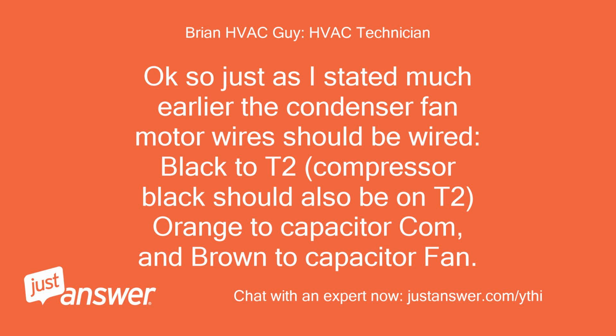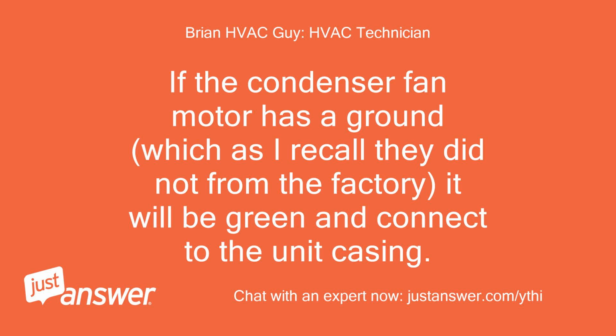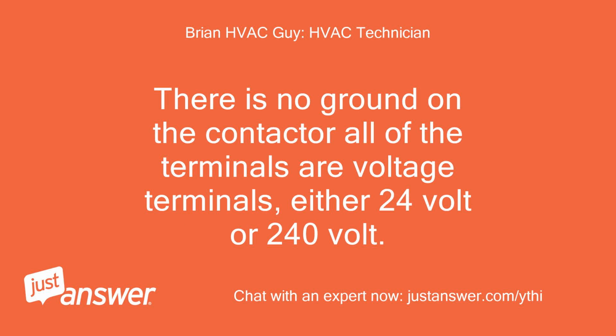Okay, so just as I stated much earlier, the condenser fan motor wires should be wired black to T2, compressor black should also be on T2, orange to capacitor COM, and brown to capacitor fan. If the condenser fan motor has a ground, which as I recall they did not from the factory, it will be green and connect to the unit casing. There is no ground on the contactor. All of the terminals are voltage terminals, either 24 volt or 240 volt.